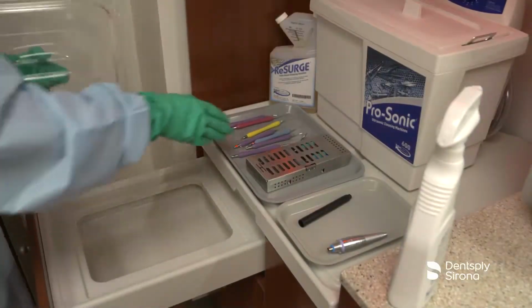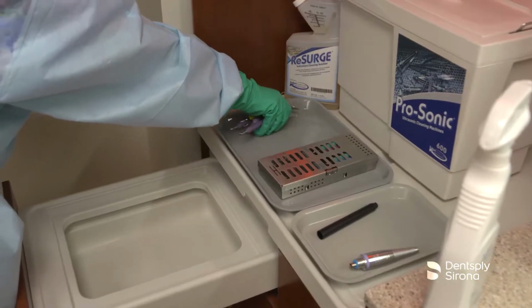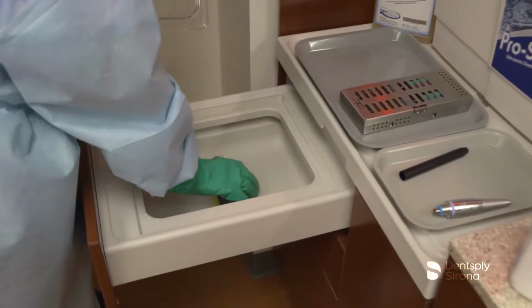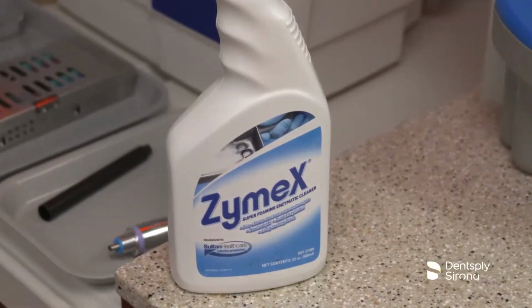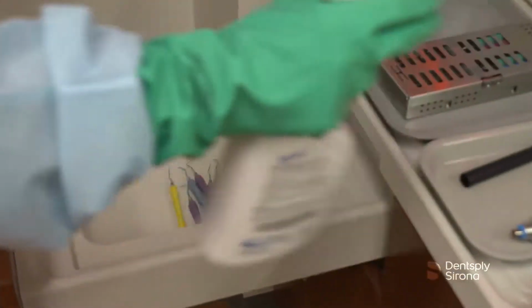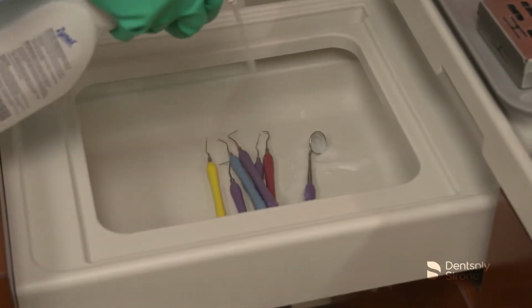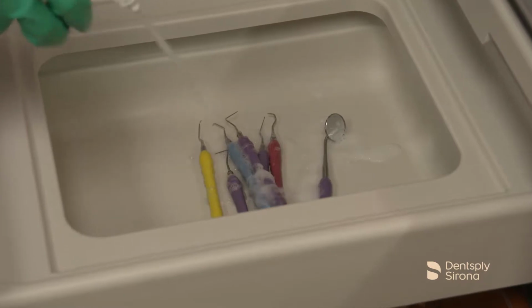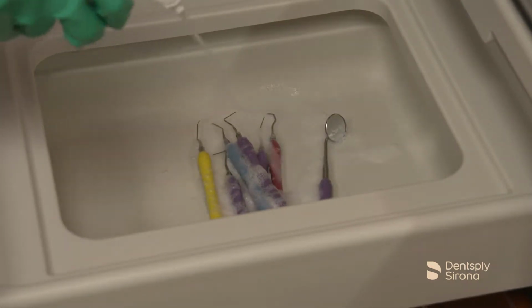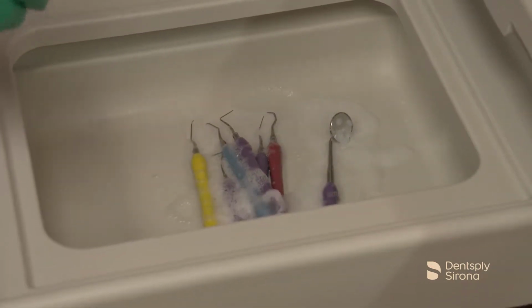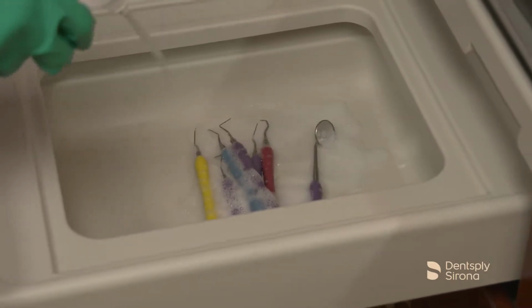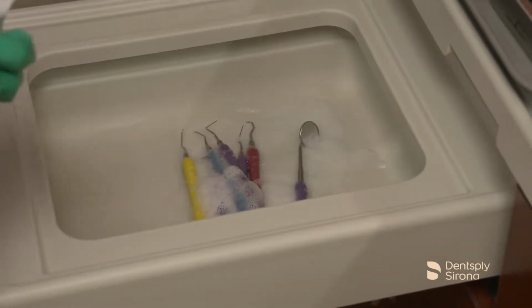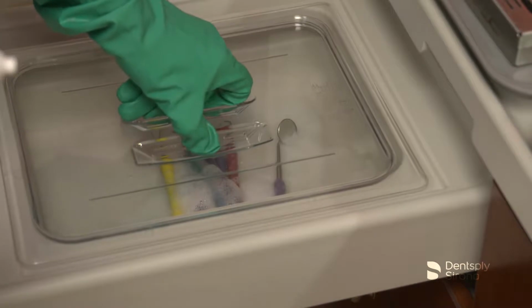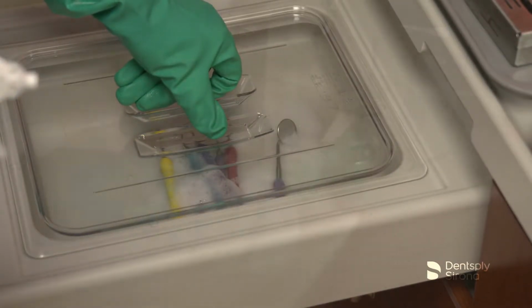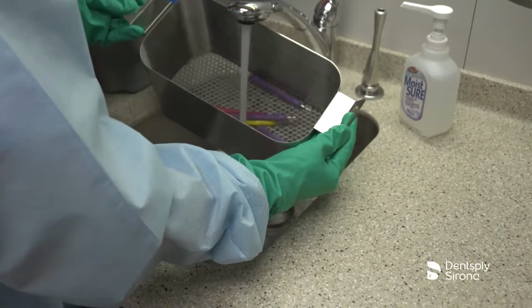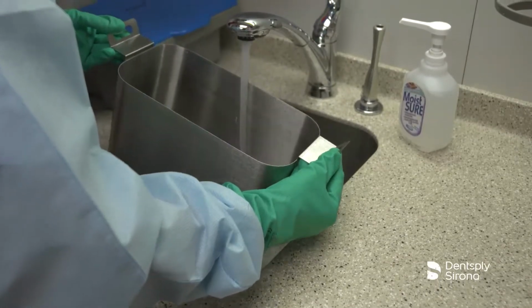If unable to reprocess the instruments immediately after use, instruments should be pre-soaked utilizing a foaming enzymatic spray like Zymex. Using an enzymatic spray aids in preventing debris from drying and begins to dissolve blood or protein and other bioburdens that may have dried on the instruments. Do not use disinfectants or sterilants for this step. Instruments should be completely covered by foaming solution during the pre-soaking process. Instruments should be cleaned prior to sterilization to remove all bioburden and debris.